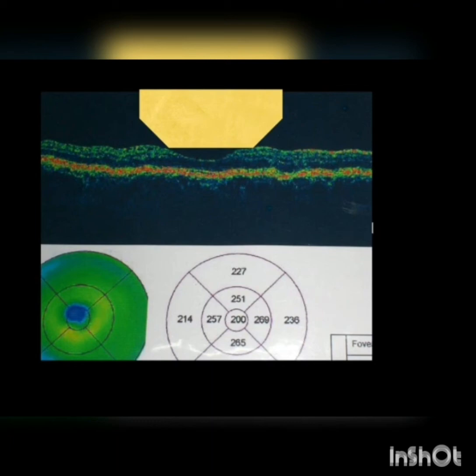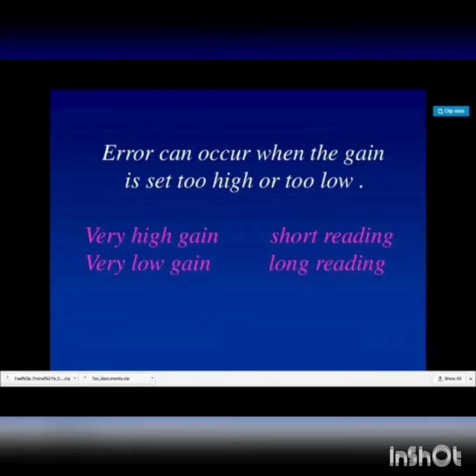When we use an optical biometer, the broad-beam problem is avoided because we are measuring the exact refractive axial length. We can also have errors if we set the gain too high or too low. If the gain is set very high, we can get a falsely short reading and a post-op myopic surprise; if kept very low, we get a longer axial length and a post-operative hyperopic surprise.